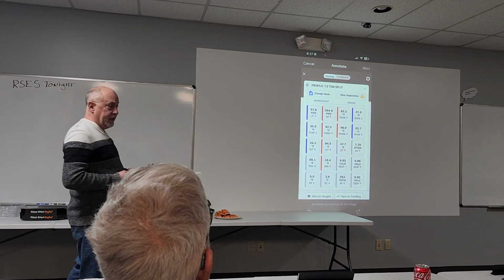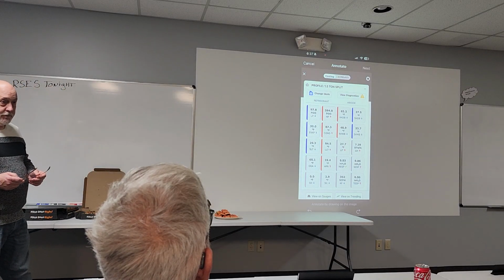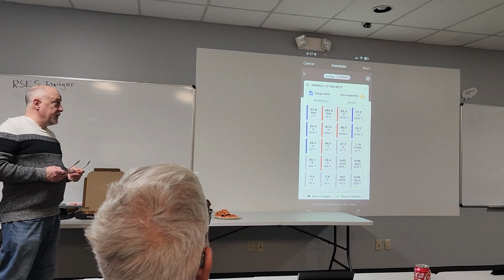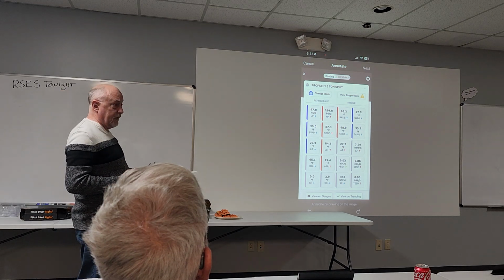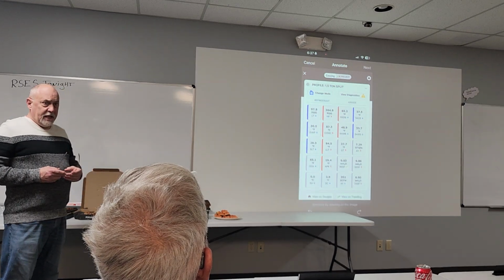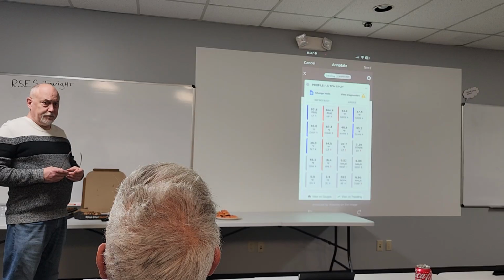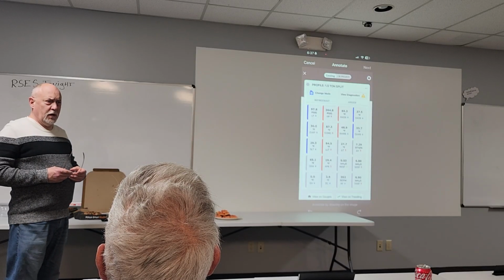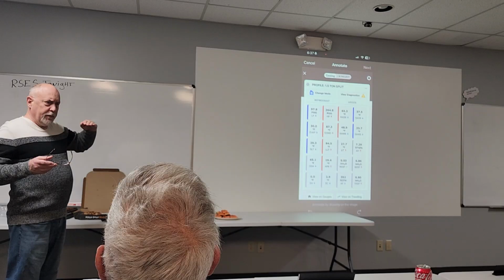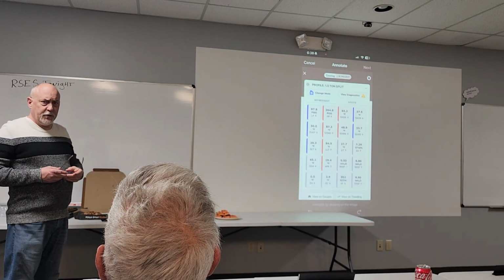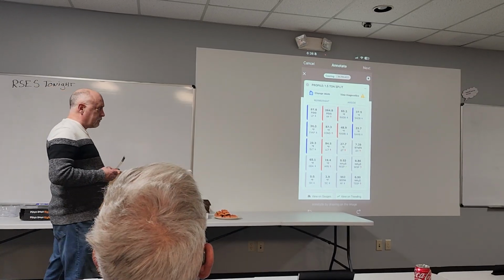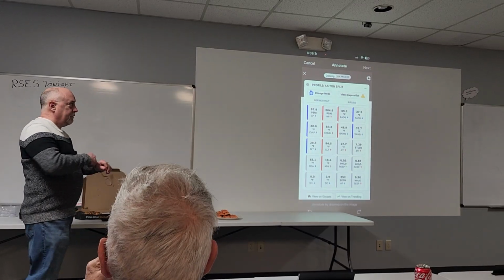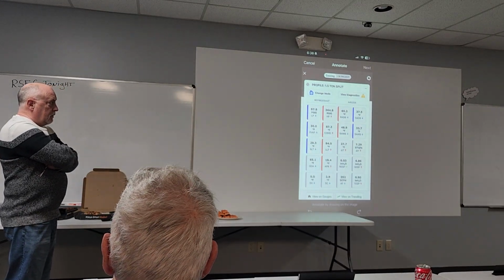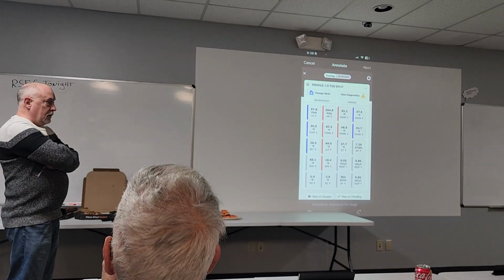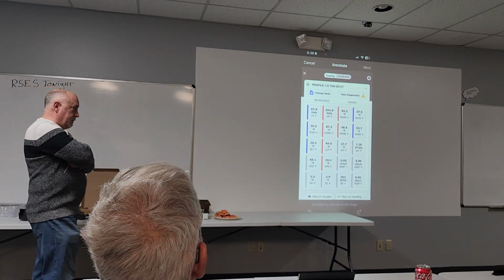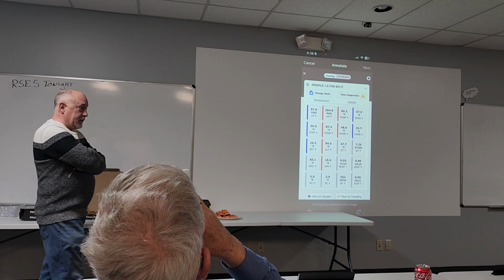So now what do we think's wrong with the system? Now, just to put this in context, this is the 13 SEER, 1.5 ton Goodman. It's got an oversized evaporator, so it's got a 2-ton evaporator. And it also has a 2-ton condenser coil. Goodman uses a 2-ton condenser coil, but puts a 1.5 ton compressor in, so they don't have to have multiple chassis sizes, right? So now we're looking at all this data, and, dirty filter and dirty condenser coil. Okay, I would say that's a pretty good guess.